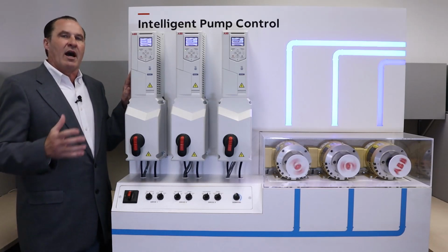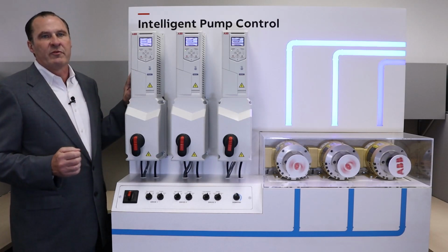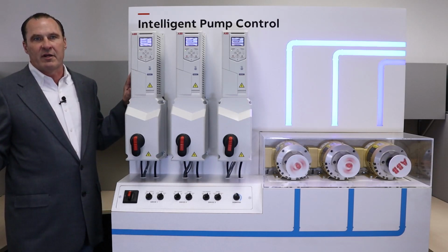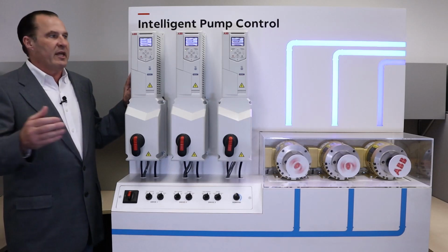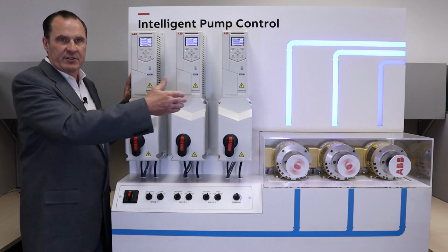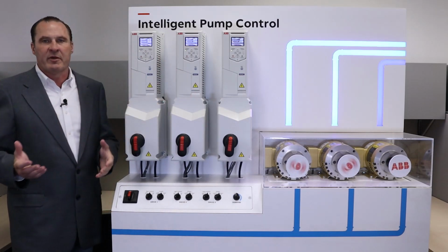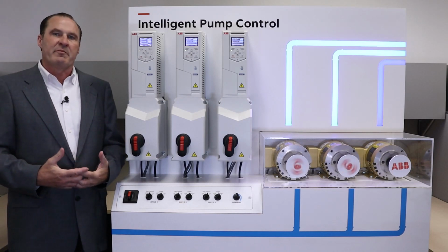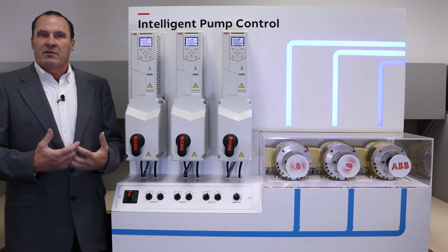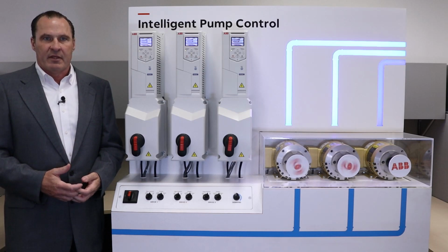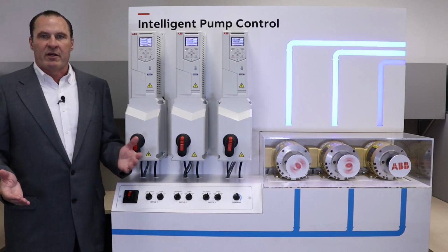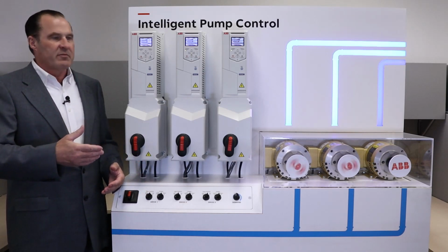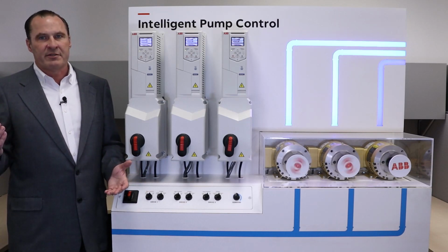The drives are the controllers of the system, removing the need for expensive external hardware, saving you money. And with the ABB moving master strategy, each drive in a multiple pump system can be eligible to be the master drive. This creates a high level of redundancy. If one pump fails or requires maintenance, the other drives in the system can become the master operating the system.